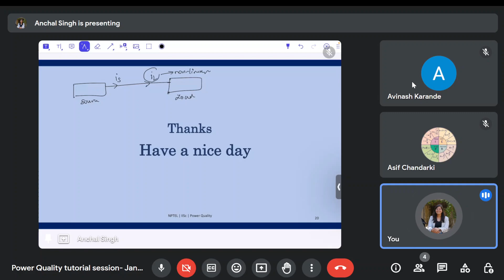Before putting the filter, while designing it, we first calculate this load current IL. All the load current calculations we did in both numericals today calculated IL. We looked at the waveform of the load current, and from that waveform we calculated what all harmonic currents are present in this load current, and using those components we designed the filter. So with the filter, IS will only be equal to IS1A, which is the IL cos theta component, only the active part, supplied once the filter is connected. So all the analysis we have been doing so far is without filter only, because the procedure to calculate the passive filter components is by finding the load current waveform and its harmonic components.